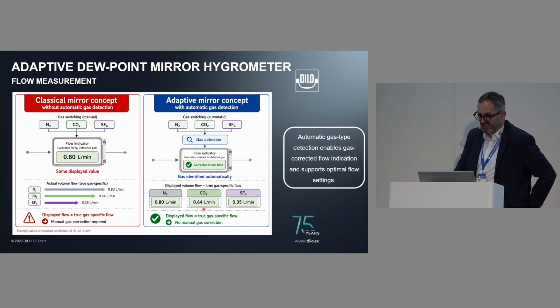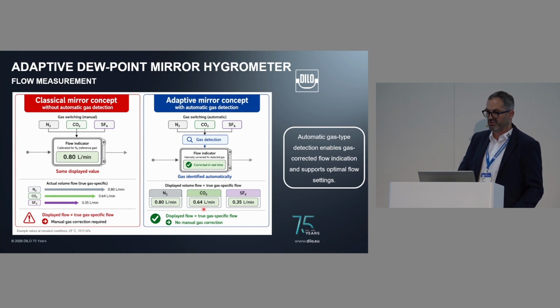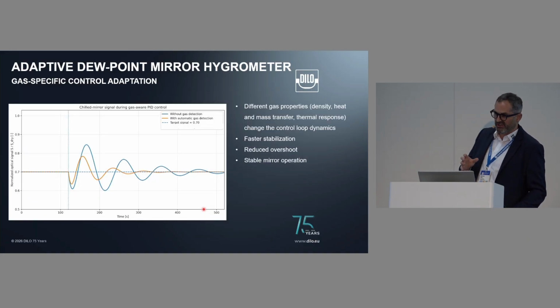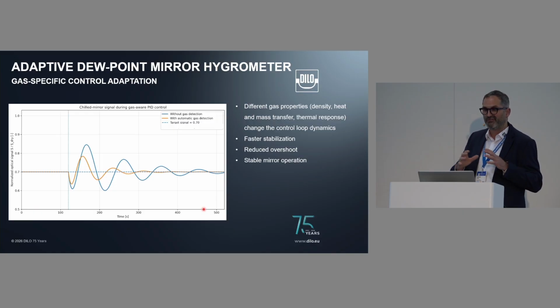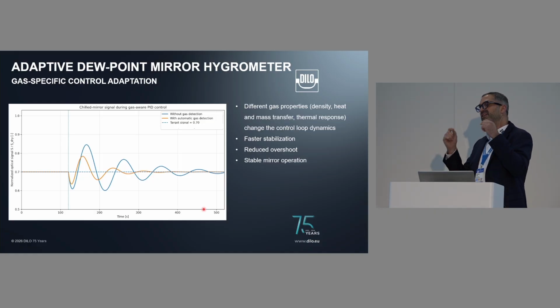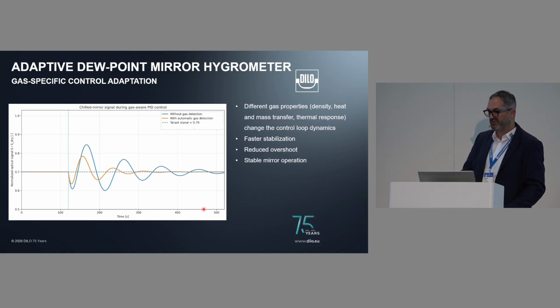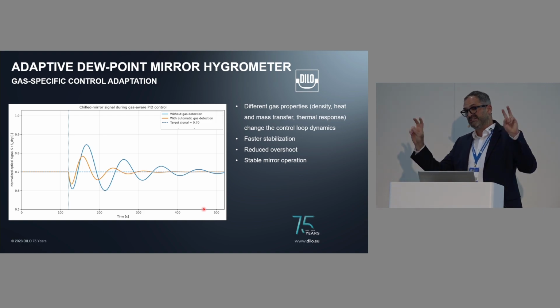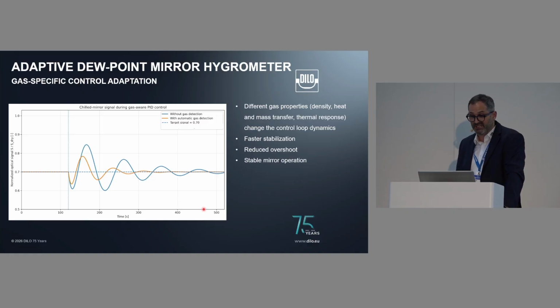Yeah, so automatic gas detection enables gas-corrected flow indication and supports optimal flow settings. Different gases have different properties, for example density, heat, mass transfer, and thermal responses, and this might also affect the control loop of your dew point hygrometer.